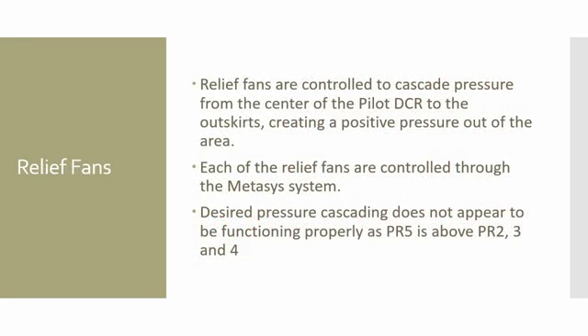MAU2, DHU12, and DHU9 make up the air intake system going into the dry clean rooms. There are also exhaust and relief fans coming out. The relief fans are controlled to cascade pressure from the center of the pilot dry clean room to the outskirts, creating a positive pressure flow out of the area. Each of the relief fans are controlled through the Metasys system.